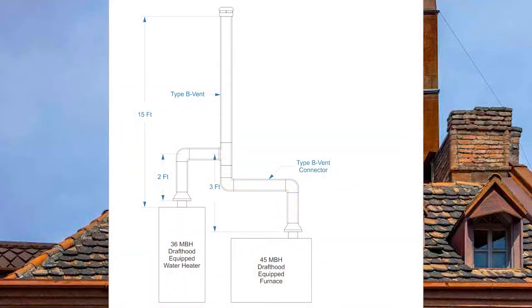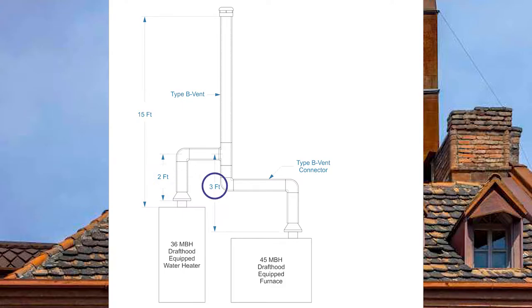The first example is two draft hood equipped appliances sharing a 15-foot common vent. We have a 36,000 BTU water heater with a two-foot vent connector rise and a 45,000 BTU furnace with a three-foot vent connector rise. Notice that we have double wall vent connectors, which means we should be using table C3.